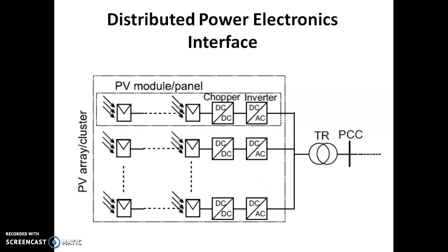This array is connected to an inverter to convert the DC power produced by the array to AC power. The inverter contains protective functions which monitor the grid connection and isolate the array if any problem occurs. It also contains MPPT, maximum power point tracking, to obtain maximum energy. MPPT maintains PV array operation at the best possible efficiency.